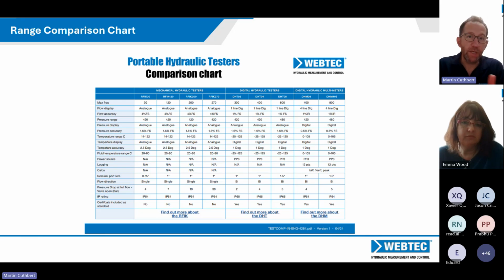You might need to think about whether bidirectional or reversible is important. There may be questions around accuracy, and for some people doing testing on case drain, there may be a maximum pressure the case drain can see without blowing up the seals. So the pressure drop across the tester may be important, and basically the turbine flow meters have much lower pressure drop than the RFIK.